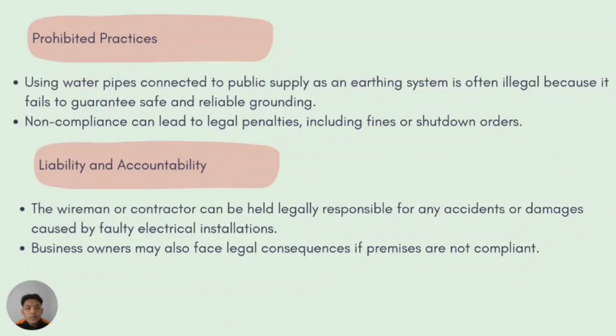Prohibited practices, using a water pipe connected to the public supply as an earthing system is often illegal because it fails to guarantee safe and reliable grounding. Non-compliance can lead to legal penalties, including fines or shutdown orders. Liability and accountability: the wireman or contractor can be held legally responsible for any accidents or damage caused by faulty electrical installations, and business owners may also face legal consequences if premises are not compliant.